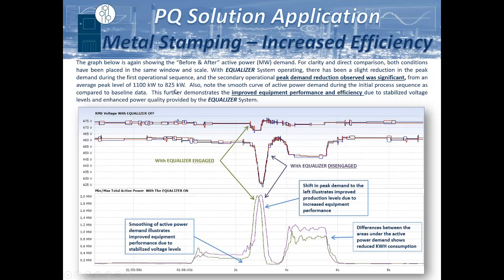This is probably one of my favorite slides because we've superimposed both the engaged and disengaged time periods. You can see that the top line is with the system engaged, and the bottom line for voltage is with the system disengaged. As it initiates the initial stamp, that voltage drop has a significant impact on the active power requirements of the system. This purple line, as it is being engaged, has a very jagged profile, and the reason is that the motor is constantly chasing this voltage drop. As your voltage varies, the torque to kilowatt ratio for all your motors is going to be impacted.